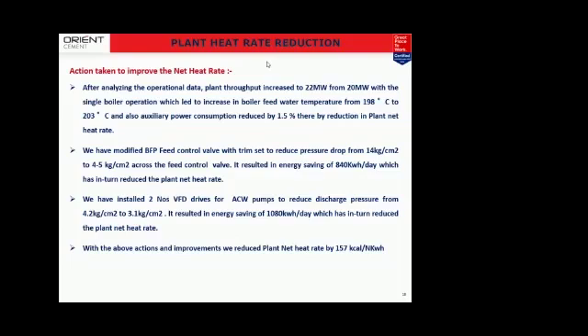And another one is we didn't have VFDs for the auxiliary cooling water pumps. So for that also we have installed 2 numbers of VFDs, and since we have installed the VFDs, we could bring down the water pressure from 4.2 to 3.1 kgs per centimeter square. That is almost 1.1 kg drop, which has also resulted in a very big saving of 1080 kilowatt hour per day. With the above improvements, those 3 improvements, we were able to reduce the plant net heat rate by 157 kilocal per kilowatt hour. So these were the contributions for reducing the heat rate.